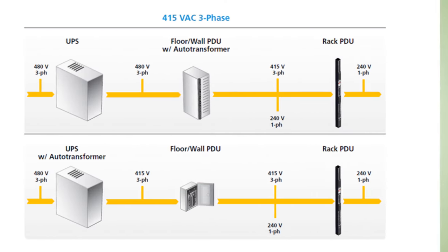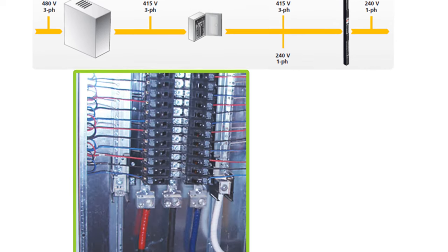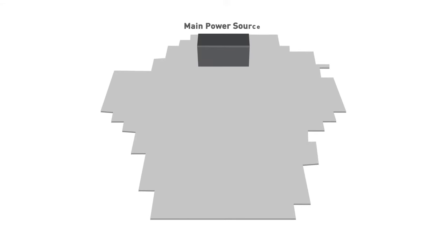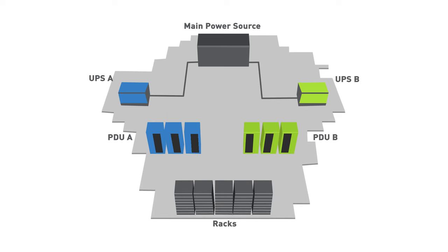If you're delivering three-phase power to the rack, then you would connect an electrical wire to three separate poles. These three wires are within a conduit that's called a whip, and these whips run under the raised floor of a data center. At the end of the whip is the outlet box. Each rack should have two outlets from two different RPPs attached to two separate UPSs as part of a redundant power chain.